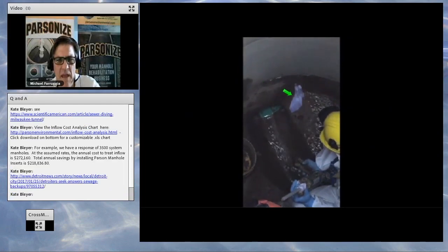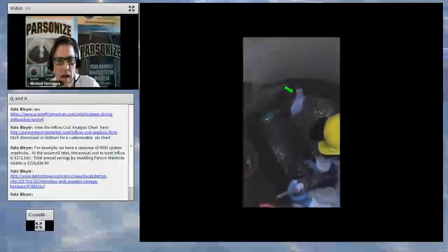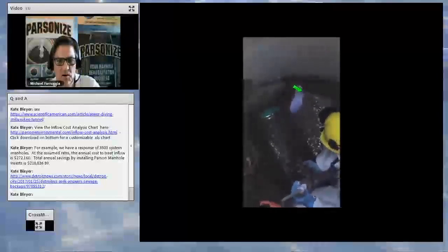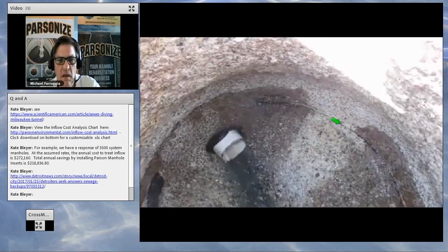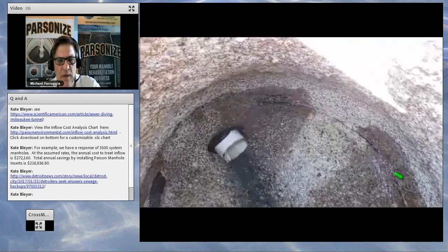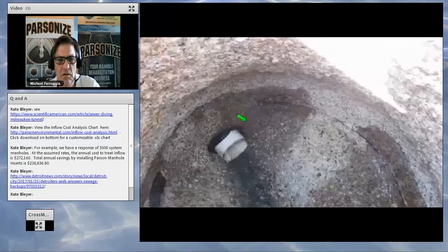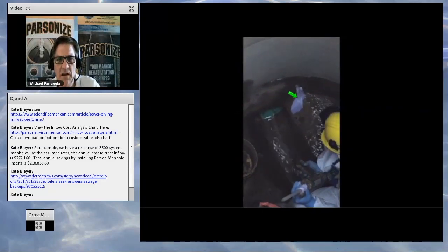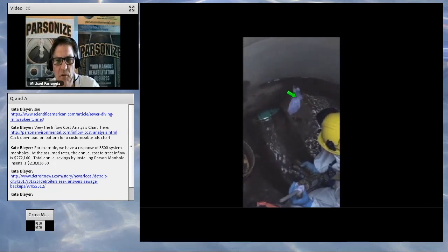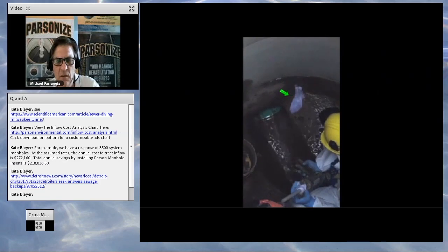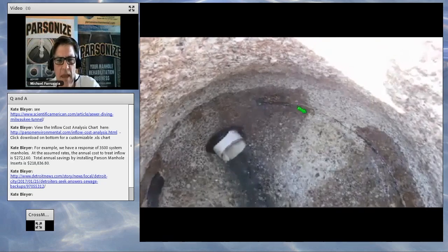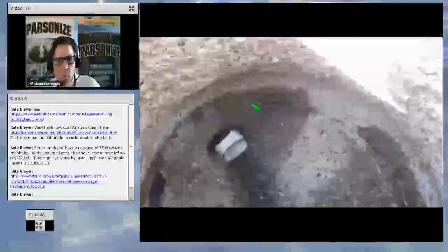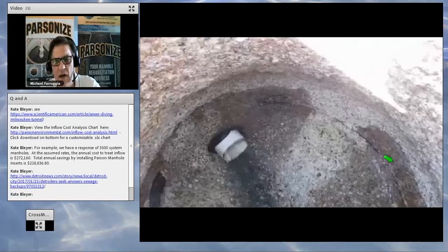Here we have a very active leak — you can see it. And later in the presentation we're going to show you how we actually stop that active leak. Here we've got a much smaller active leak running along this crack, and we have a hydraulic cement we're going to show you how to stop. The very active leak is somewhere around 35 to 40 gallons a minute, and we're going to inject it with a chemical grout and stop that leak. This smaller one is probably about a gallon a minute — a much slower leak — and during the repair, we're going to chase the leak right down that crack. In about 15 minutes later, it'll be completely stopped.